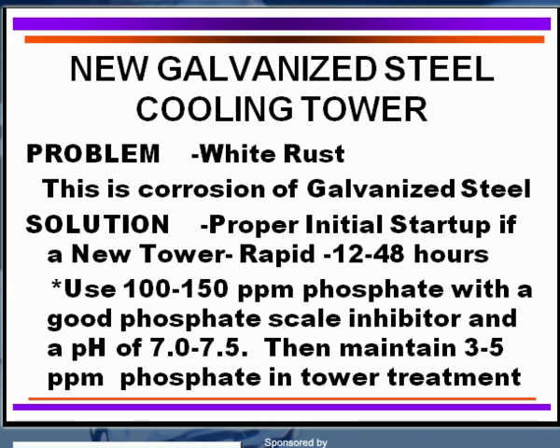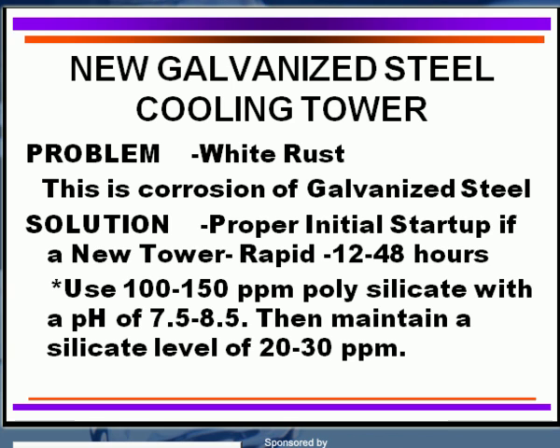There is another technique that can be utilized, and that is using a different chemical such as polysilicates. Again, we can use a high level of polysilicate initially, controlling the pH a little bit higher, because silicates are of course much more soluble at higher pHs. Therefore we don't really have to have any scale inhibitors for silicates in this particular method of establishing protection on the galvanized steel. We'd like to maintain about 20 to 30 ppm of silicate in the treatment program thereafter, and sometimes phosphate can be used to continue to maintain that program alongside the polysilicates.